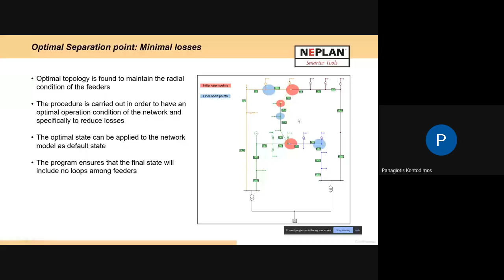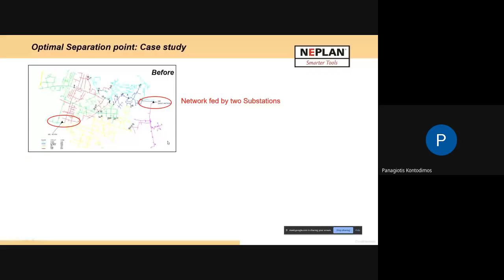But very often in utilities, we need to know if there are open points, if we can make the switching in a different way to keep the radial operation, but at the same time improve the network in terms of losses. This is optimal separation point, which is able to suggest the switching of the network in order to improve the losses.